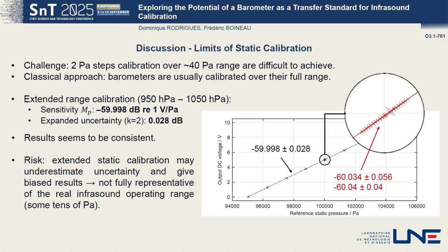So you can see here the black points reaching a sensitivity of minus 59.998 dB, slightly different from the one obtained previously, here the red data. So anyway, there is a small bias. It is covered by the uncertainty, so it is consistent, no problem. But I would like to highlight one fact: there is anyway a risk, specifically when the barometer is not perfectly linear, to have a bias or to underestimate the uncertainty with such an approach, because some information is missing when providing such a classical calibration.